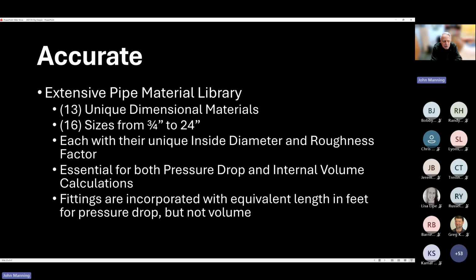Also, in the area of accuracy, our program includes 13 unique dimensional materials in the way of piping, 16 different sizes from 3/4 inch up to 24 inch. They each have their unique inside diameter and roughness factor, and these are essential for both pressure drop and internal volume calculations. We take into account the fittings, whether it's an elbow or a T. We use the equivalent length method to calculate the impact on pressure drop, but we don't include those equivalent lengths when we calculate volume, further improving the accuracy of these calculations.